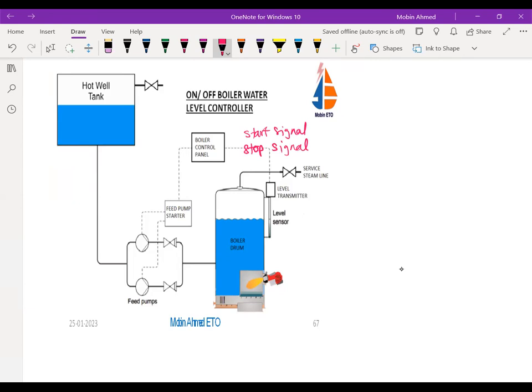It will come to the boiler control panel, and from there it will go to the feed pump starter panel. Or directly this level transmitter will go to the feed pump starter panel. It can go, or it can route through the boiler also. And this pump is switched on and off as per the required level. Okay, it is going to be on and off. So this is the on-off control.